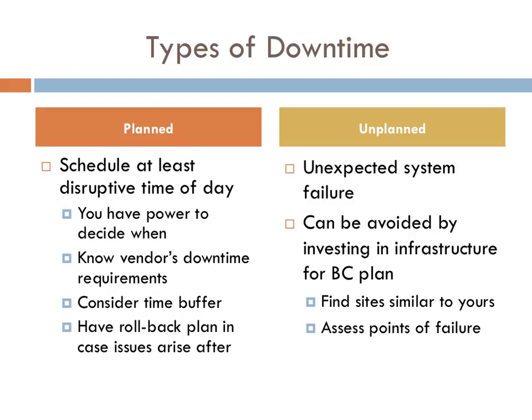Sometimes a vendor can require an upgrade that can take up to a few hours of downtime, so make sure you plan accordingly and know ahead of time how long the upgrade will be. Consider time buffering. Plan the downtime not only at the least disruptive time of the day, but also allow some additional time as a buffer in case the downtime takes longer than expected.